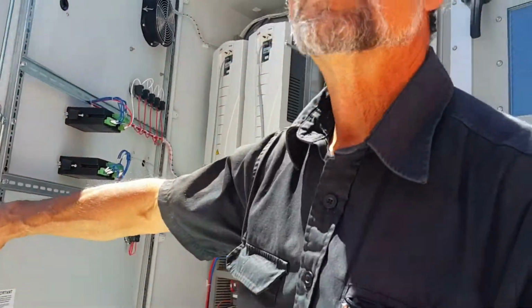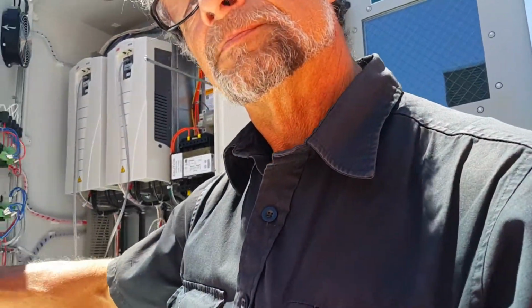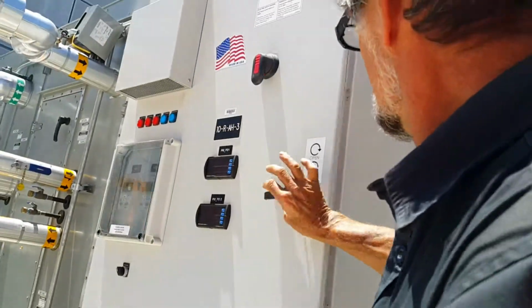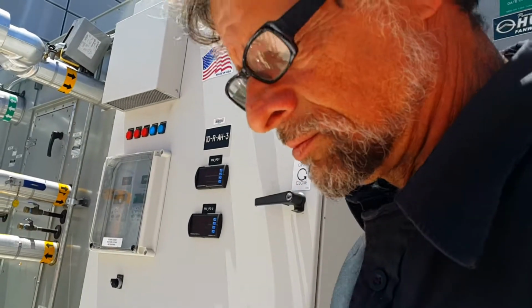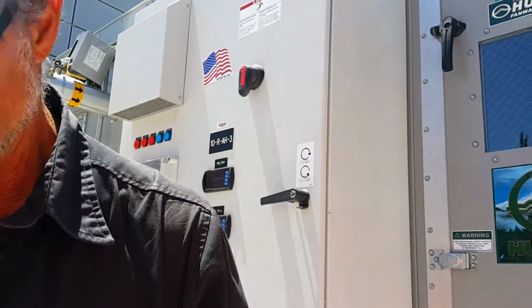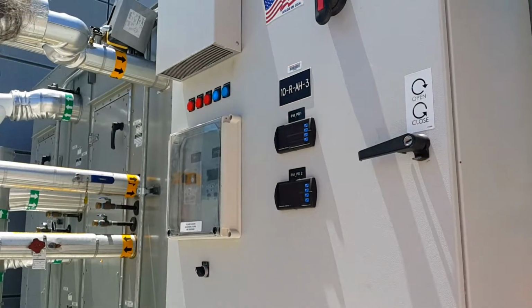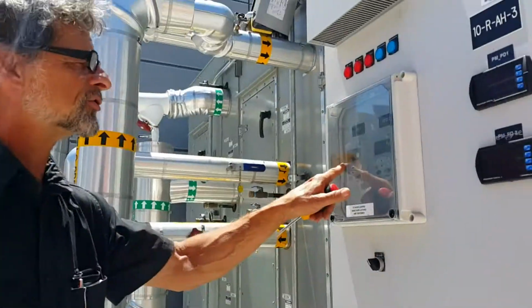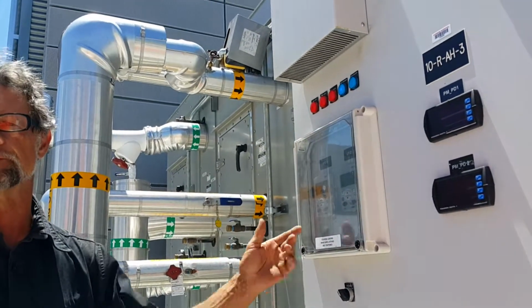So you were saying something about the lights, how you don't trust them because they burn out, right? What's a better way of checking whatever that fault is? Well, you would also get a fault on the drive display and still lit up.